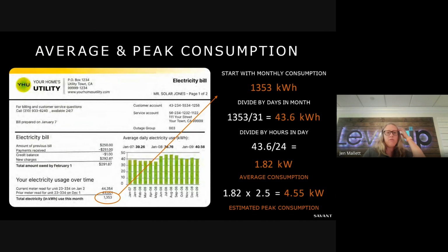Average and peak performance consumption—this is a great calculation. You start with the monthly consumption of the particular property, which you can find on your home utility bill. In this case it's 1353 kilowatt hours. You take that and divide it by the days in that particular month, then divide by the hours in the day, and that gives you your average consumption. In this case, it's 1.82 kilowatts average consumption.